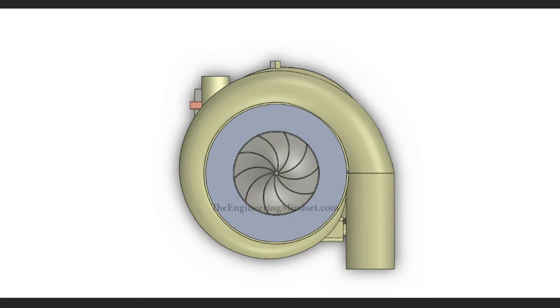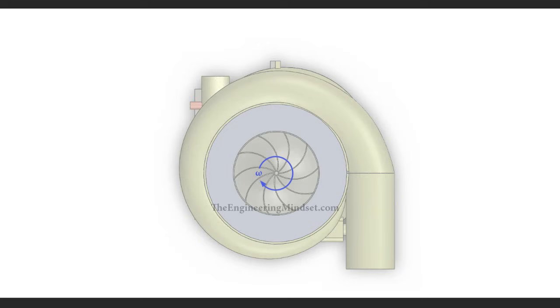So what's happening to the refrigerant as it enters and gets flown around by the compressor? Well, we know that when the impeller spins, it's going to have an angular velocity, right? And another key aspect of the compressor is also the diameter of the impeller. These can vary in size, and the reason it varies in size is due to the type of refrigerant that you're using. Different refrigerants will have different molecular weights, and also the amount of lift or head pressure you want to create, and the amount of refrigerant that you want to flow through the chiller, producing the cooling effect. So the size of the impeller is also really important, and we're going to look at some equations shortly. We're just going to use this letter R to indicate the radius of that impeller.